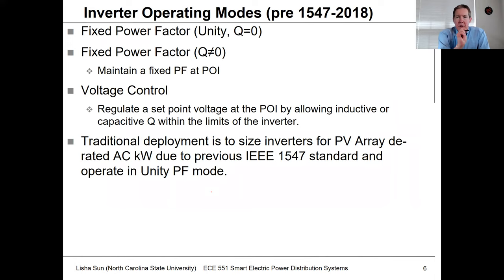As far as the operating modes, if we're talking about pre-2018 standards, we didn't really have that much flexibility. Most of the time, these PV plants were operating at a unity power factor. So power factor equal to one, there'd be no reactive power injection. However, you did have a few sites that were operating at fixed power factors.